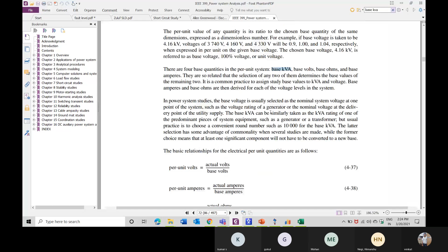What they say is you have to take the base MVA as the rating of one of the generators or transformers, but common practice is to use a round multiple of hundreds as the base KVA. This is because if you choose any particular rating of a transformer or generator, you then have to convert all other equipment to that same particular rating.